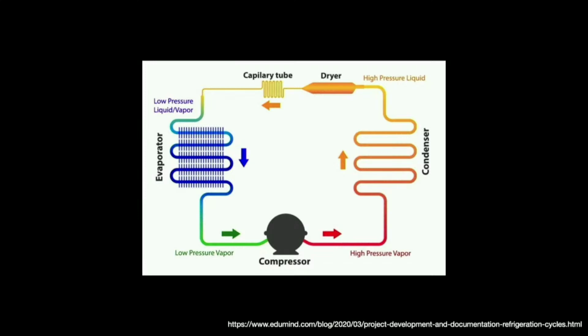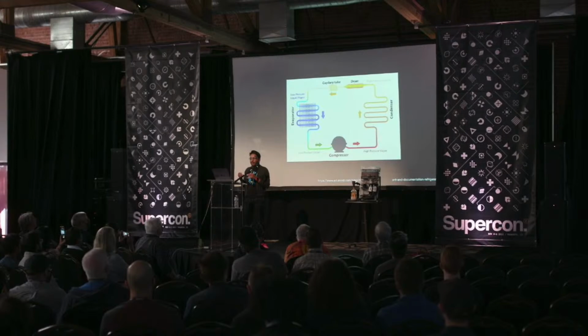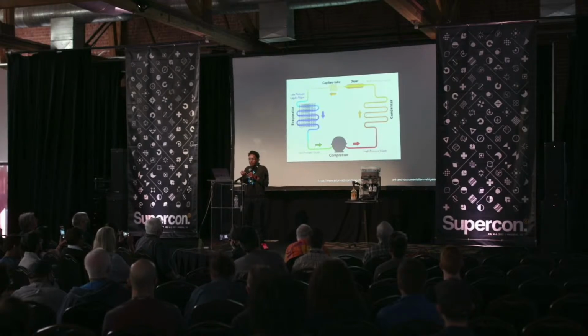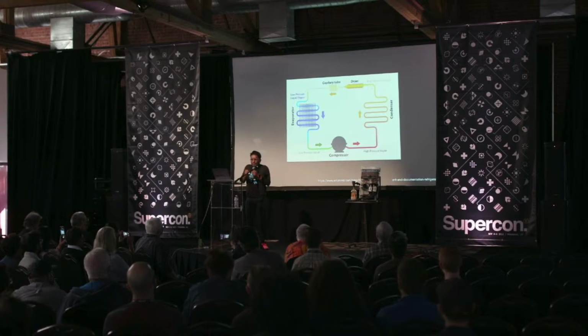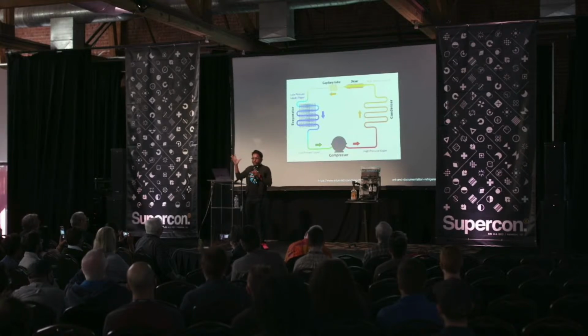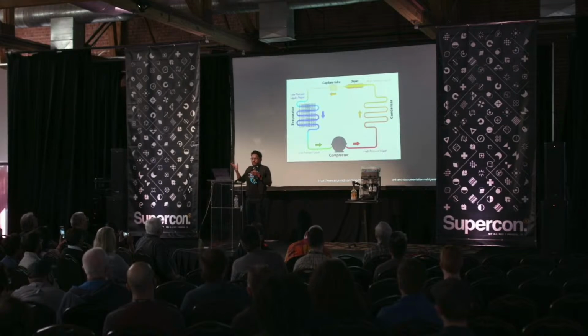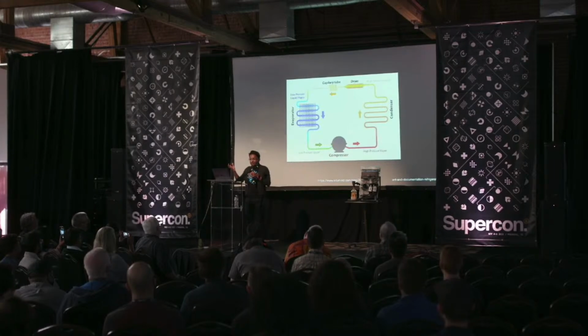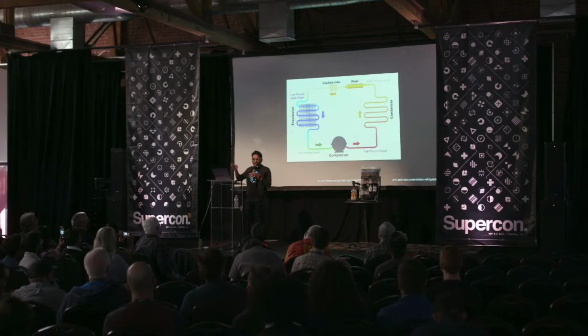So now you have high pressure liquid refrigerant that gets pushed through a dryer, which is only there to remove any moisture, because moisture can corrode and things like that. Then it gets pushed through a capillary tube or other expansion device, which just presents a lot of resistance to the flow. So this high pressure liquid is squeezing through the capillary tube, and at the end, it finds itself in a low pressure environment, and it expands very rapidly. When it does that, the rapid expansion creates a lot of surface area, and breaking those intermolecular bonds requires energy. That energy is taken from the evaporator or anything that the evaporator is trying to cool. And then your low pressure vapor just gets back into the compressor.